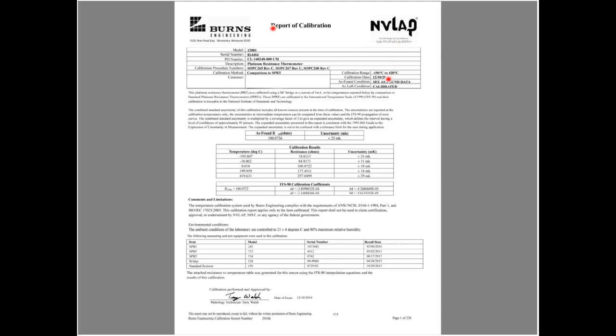Up at the top on this form, there's some basic information about the probe and how the calibration was done. This says it was comparison to an SPRT, which is a standard platinum resistance thermometer. The temperature range, and then there's some information down here about how the uncertainties were calculated.